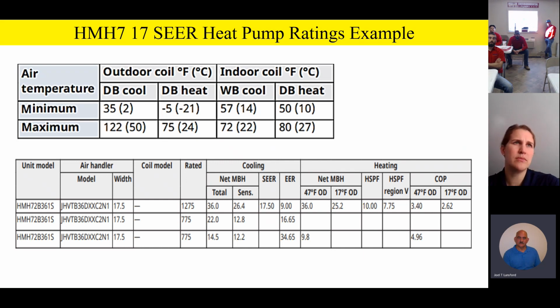In addition, down below, we gave an example of some of the rating examples. And this, by the way, is right there in the application guide that you can get the product information off Navigator. But you'll see this is just a typical 3-ton model. Even though the actual rating at 3 tons is going to be like 17.5 SEER for this particular model and that particular air handler combination, you're going to notice that even as you start getting down into the reduced capacity, it's still going to have a really high EER. And that's pretty remarkable, because the standard full-blown EER is 9.0. But when you're down there at like half capacity, it's like 34.5 EER. It's just crazy high EERs.